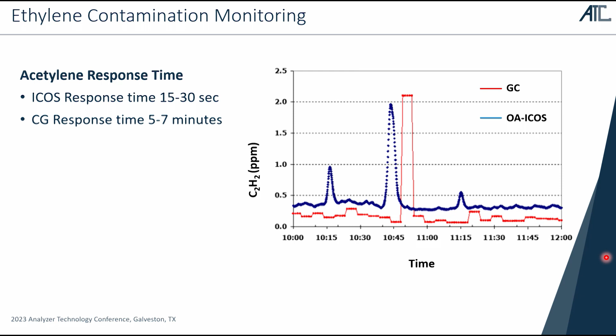If we look at sensitivity, and this is all process data, this is not lab data, it's in the literature, it's referenced in the publication to go with this. We're looking at about 60 part per million acetylene in ethylene. You're looking at a sensitivity of about 1.5 part per billion. And remember, the range that we're calibrated over is 0 to 30. So here we can trend this. We can see the stability even though we're outside the calibration range, and that's one of the advantages of using partial least squares. As this drops down in acetylene value, down to about 10 part per million, we see a sensitivity or repeatability between measurements of about 1.1 part per billion, about 1 part per billion.